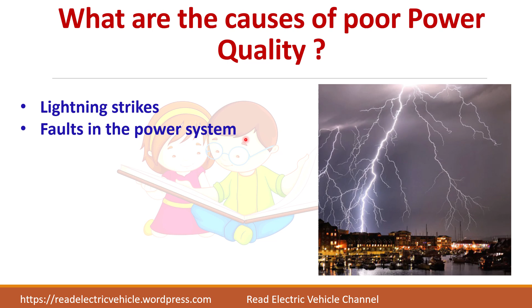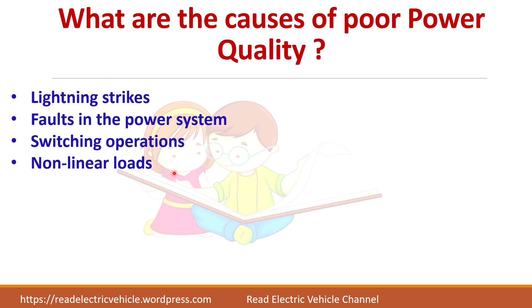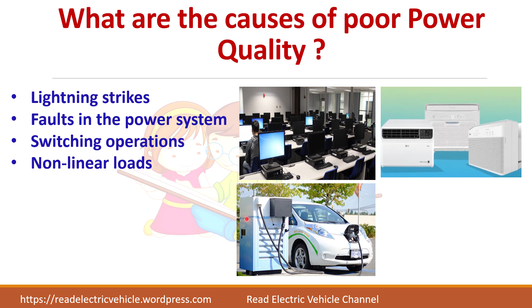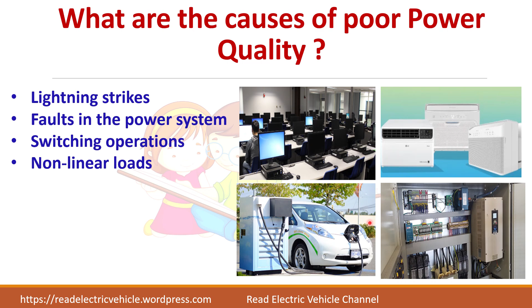Next, we will see what the causes of poor power quality are. The first thing that comes to mind is lightning strikes, which are not in our control. Next, faults in the power system can also lead to poor power quality. Switching on a large load can also affect the power quality. The last one is the non-linear load, which is the major cause of creating pollution in the power system. Non-linear loads are computers, inverter-fed drives, and EVs, electric vehicle or battery devices. All these are major reasons for creating pollution and introducing harmonics into the system.